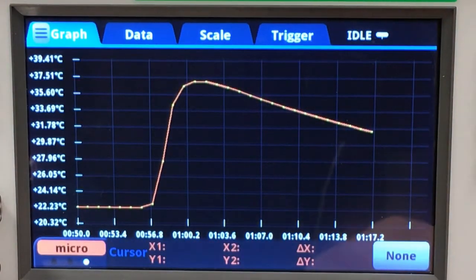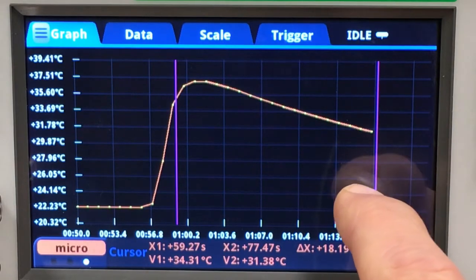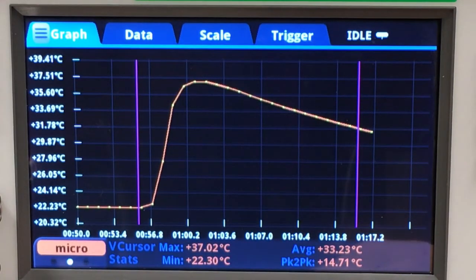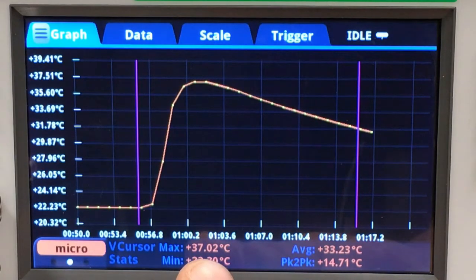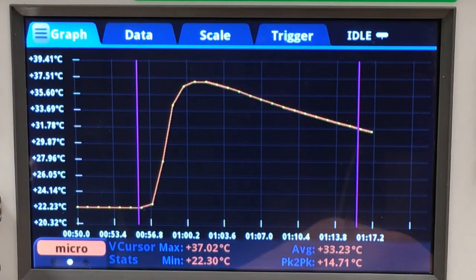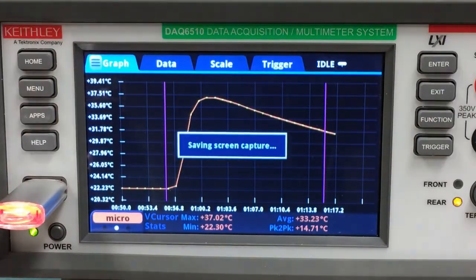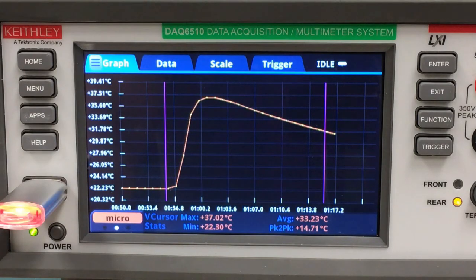Let's zoom in to get a better feel of what's going on here. Let me apply cursors — just the verticals — and we can see that these vertical cursor stats tell us we have a min and max topping out at 37.02 degrees, the average about 33.23, but our box is saying this is too hot. So we can take a snapshot by pressing Home and Enter, save the image on the UI to our USB drive, remove it, and email it to a technician who can fix the problem.